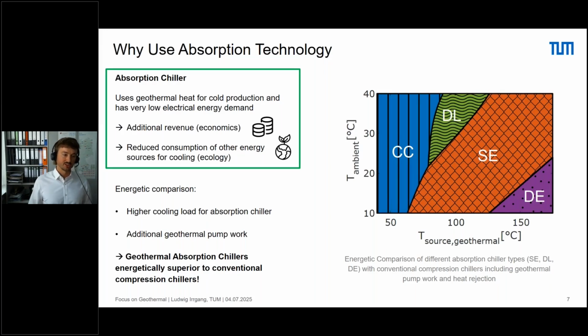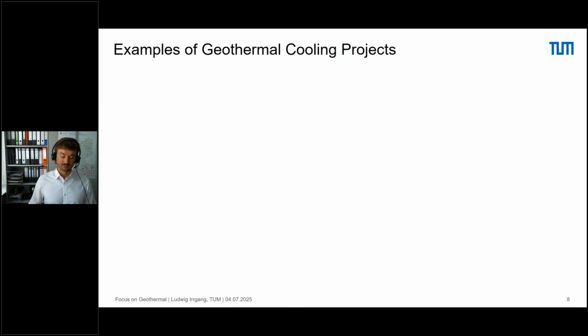If we compare compression chillers with absorption chillers energetically, we have to look at higher cooling loads for the absorption chiller and consequent higher electricity load for cooling. But to be fair, we also have to include the additional pump work of the geothermal source. We did analysis in a recent paper, to be published soon in the International Journal of Refrigeration, comparing compression chillers to all kinds of absorption chillers. We found that absorption chillers are still energetically superior, and that the single effect cycle is most relevant for typical geothermal boundary conditions. In the future we will also publish results on economic and environmental analysis of compression versus absorption chillers, but for that I have to point you to future publications.